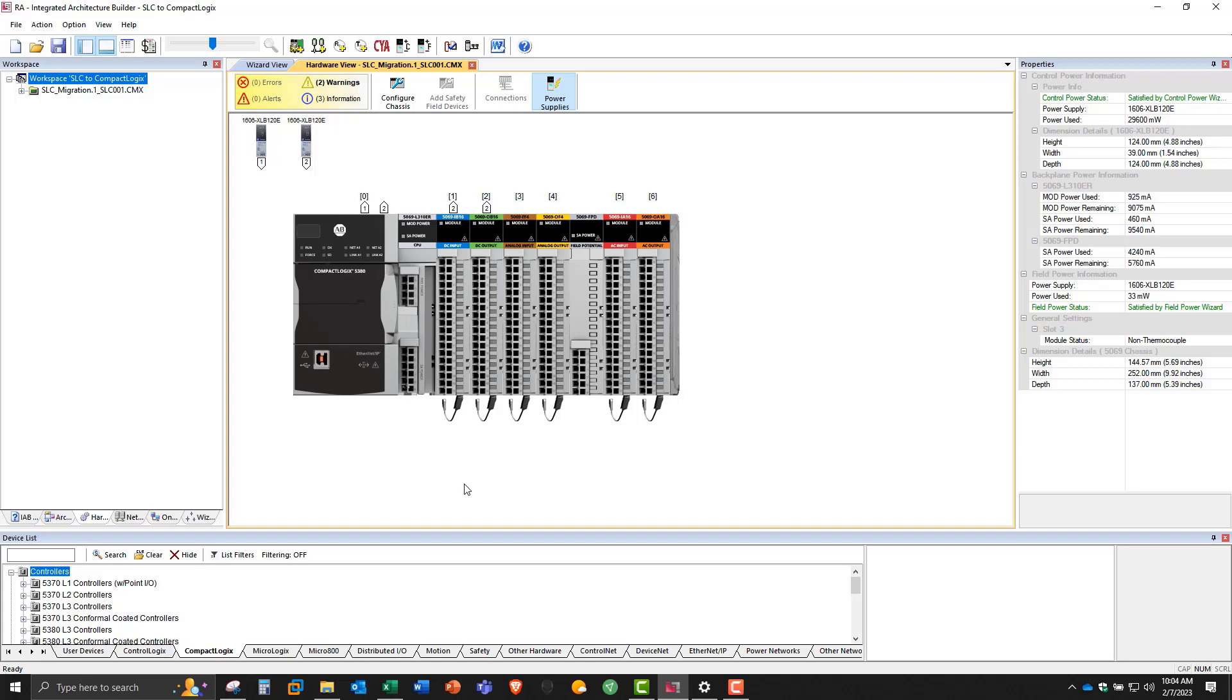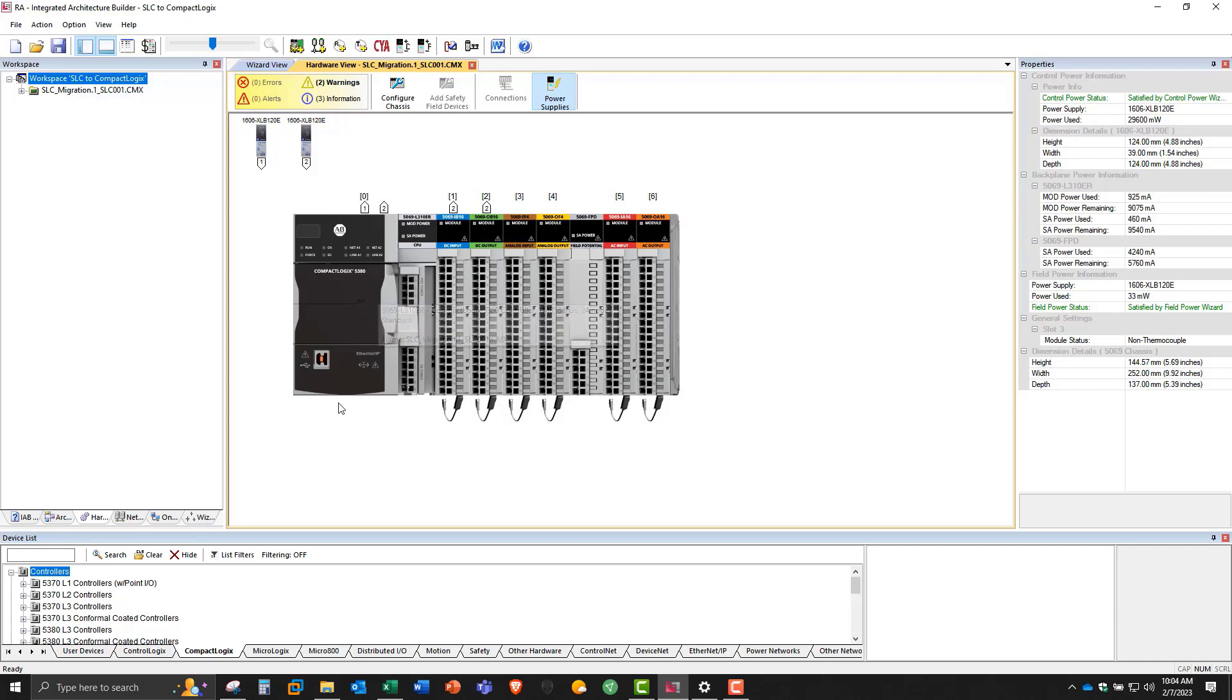If you use one power supply for both, if you have a problem with the power supply, your whole system goes dark. You lose control. And if you have a separate power supply for MOD power, and the field power goes out, there's diagnostics in the controller to tell you that there's an issue with the field power. And your IO cards will reflect that. So again, that's a reason why you'd want to have two power supplies.